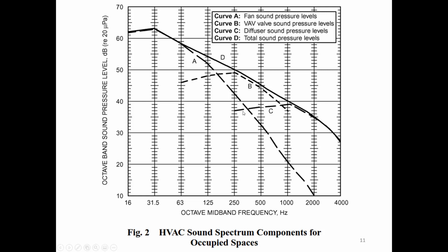And C is the higher frequency stuff—that's the turbulent noise, say at the diffuser, the grill that the air comes out of in the room, and the elbow right above it. There's turbulent airflow noise generated right there, and there's not much you can do about it at that point other than slowing the air down. So that turbulent noise is what makes up this higher frequency part of the spectrum of noise in a space.